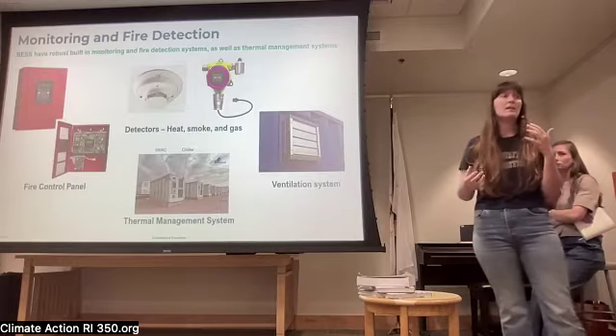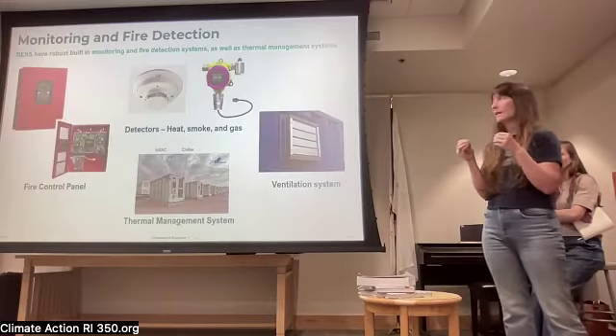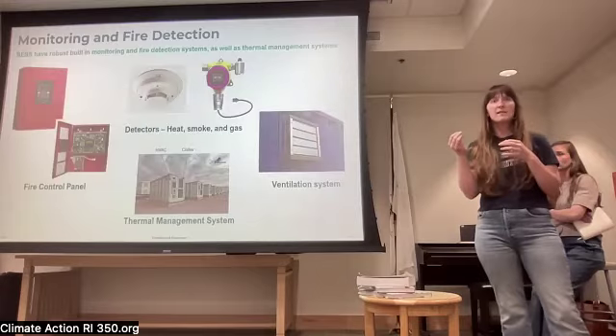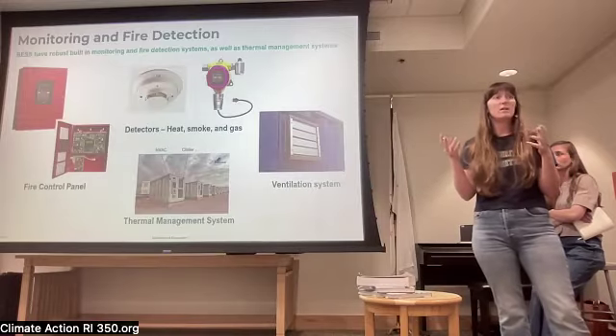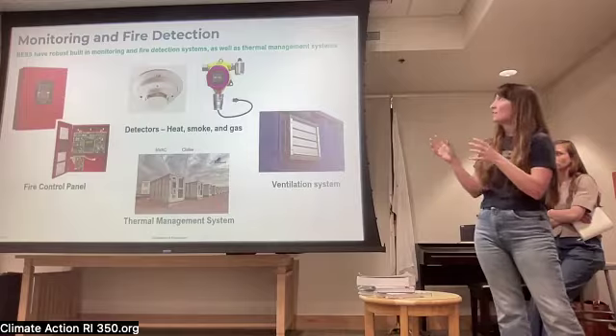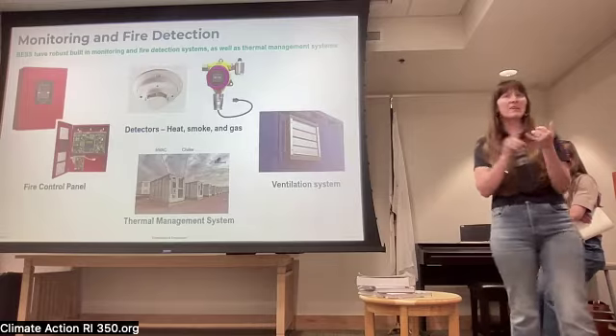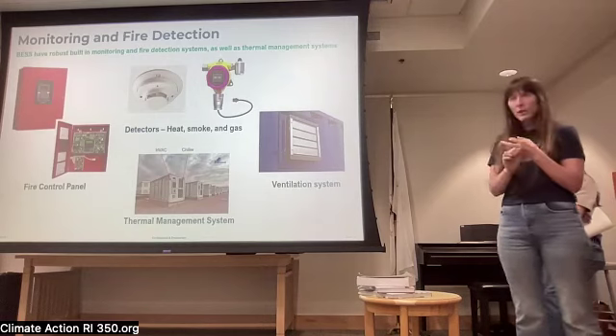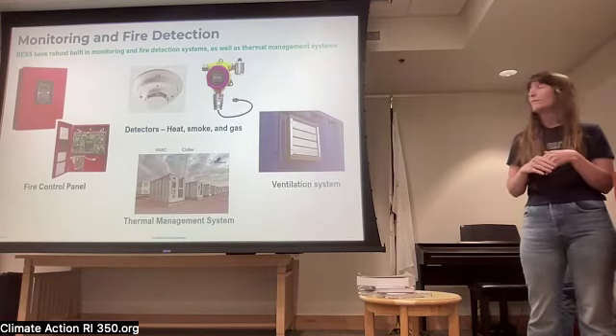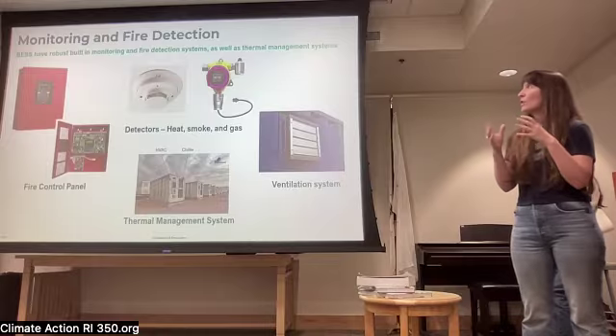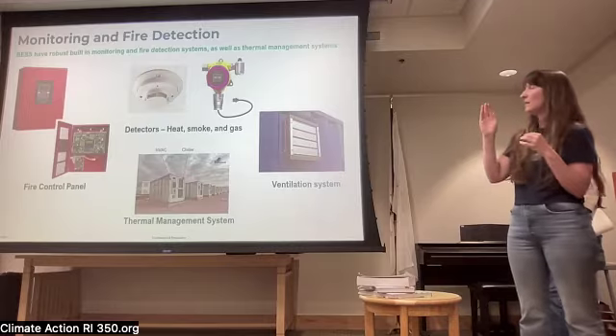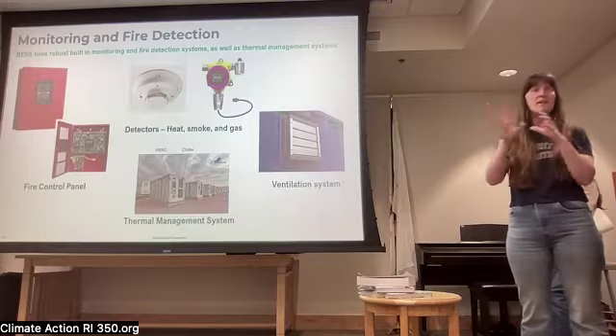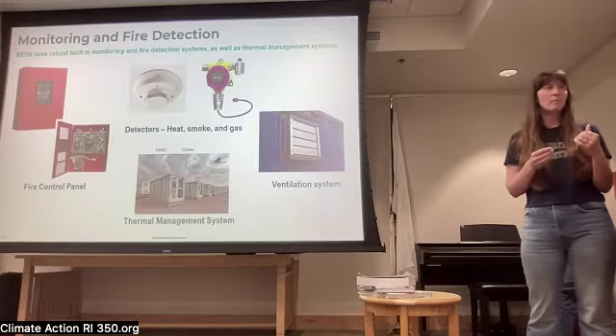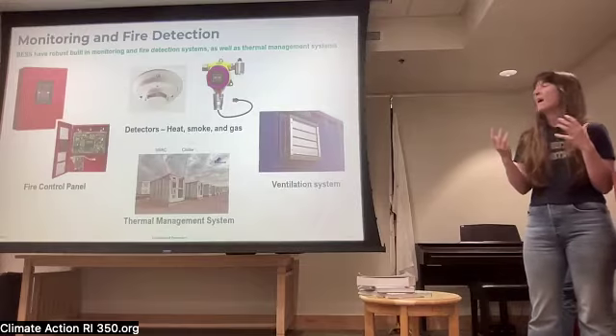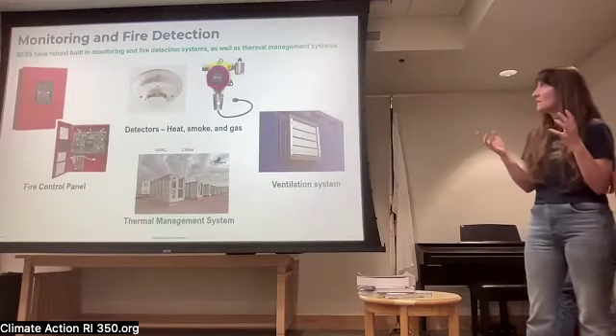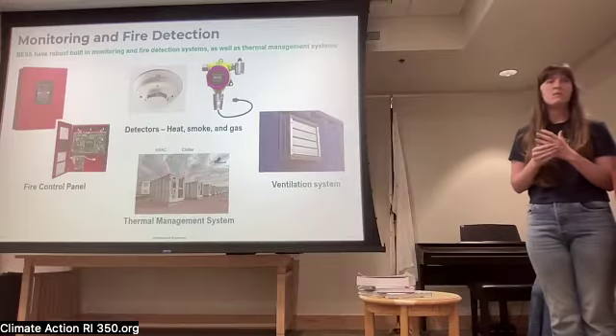Thermal runaway is when a battery enters a state of overheating - it'll begin to off gas and then can catch fire. So all of the systems today are designed in alignment with National Fire Code, or whatever the state fire code is - for this project, Massachusetts fire code. There's also UL certifications that both the battery cells and the entire enclosures have to go through, including large scale fire tests. It's very robust systems to ensure the safety of these products.